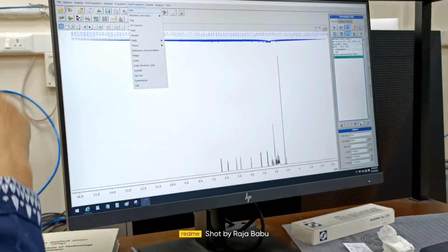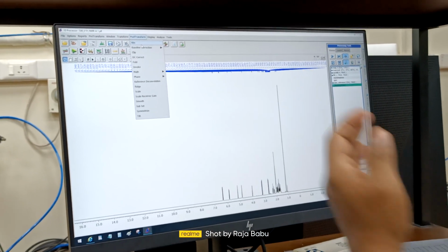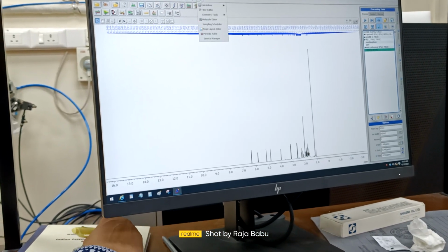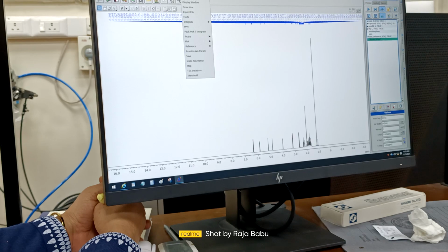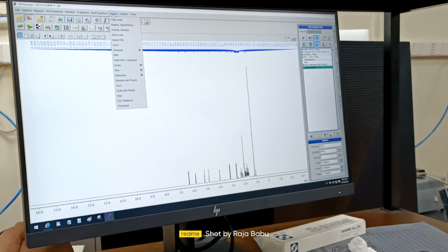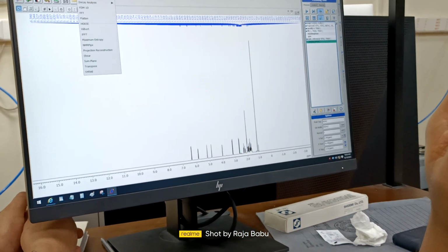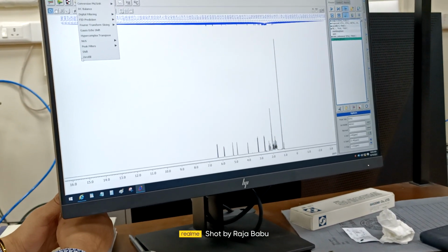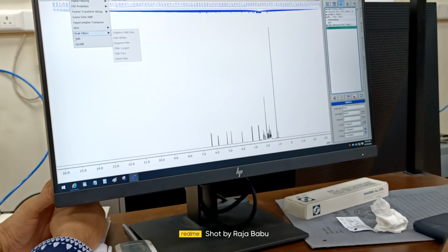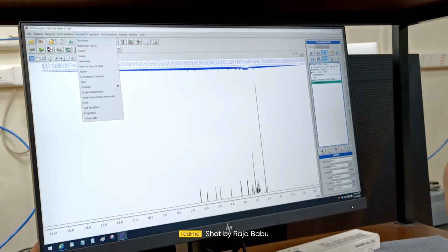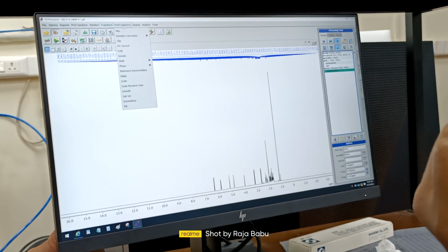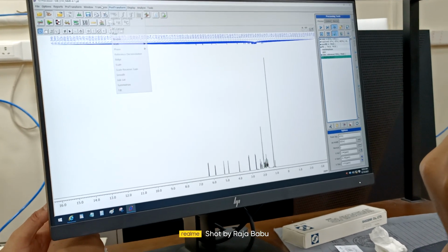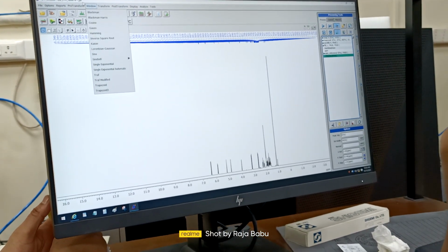The others are before that, yes. So you can see it. The window and zero fill and so on have to be applied before the transform. Zero fill is in window functions here, so we will put it before, yes, zero fill, this one. This is in the pre-transform. You look in the drop-down list and try to find it. Okay. Suppose if it is after transform, then this has to be applied after FFT. Importantly, the before ones have to be applied before the FFT.